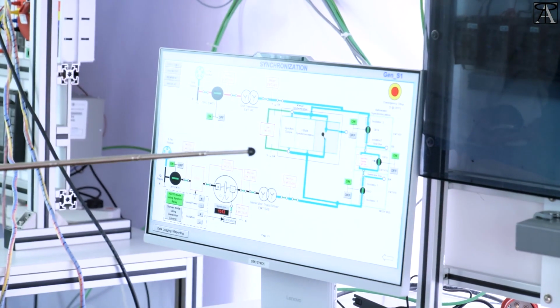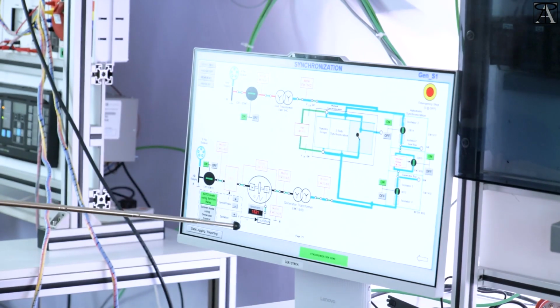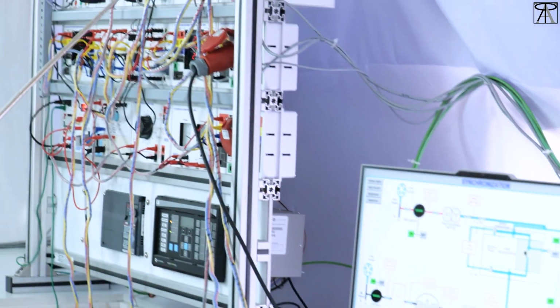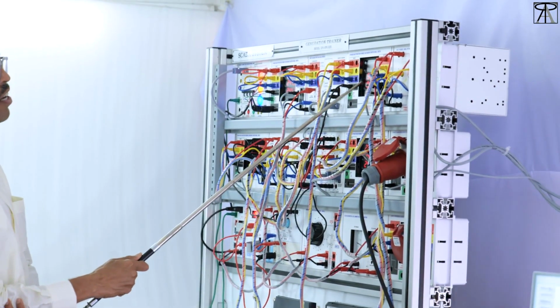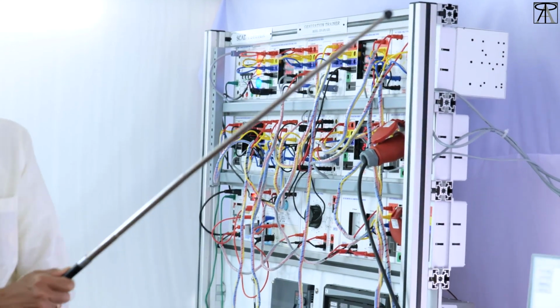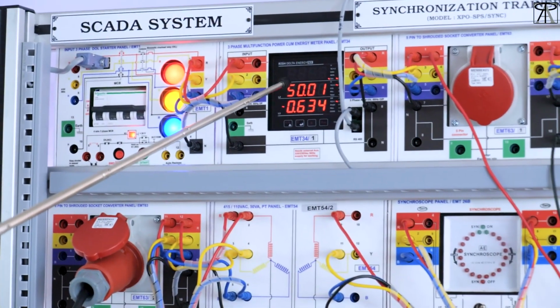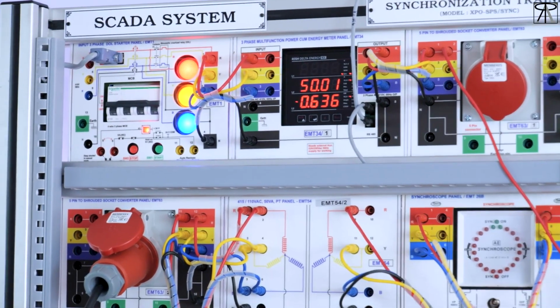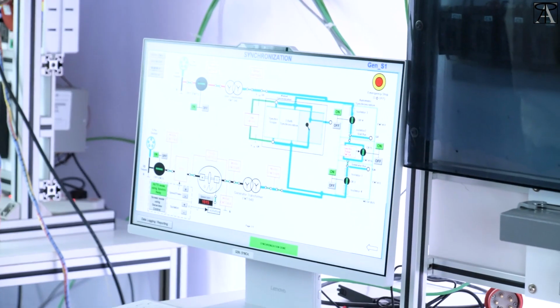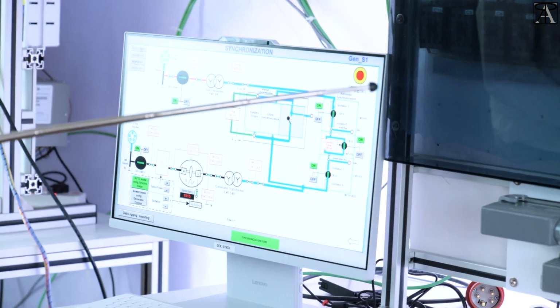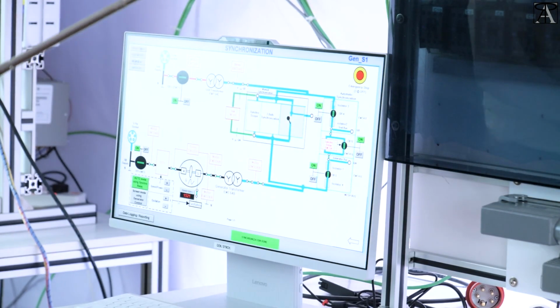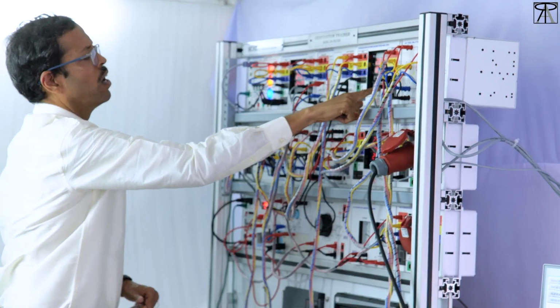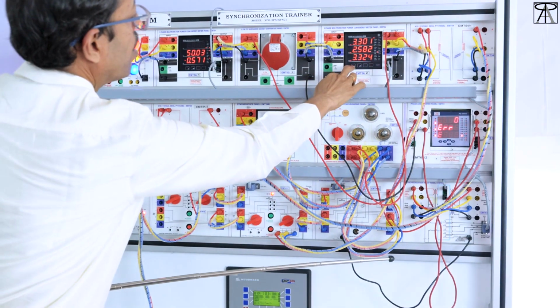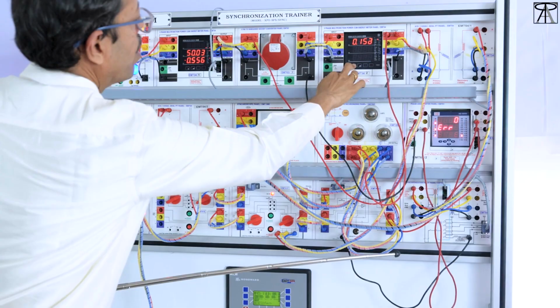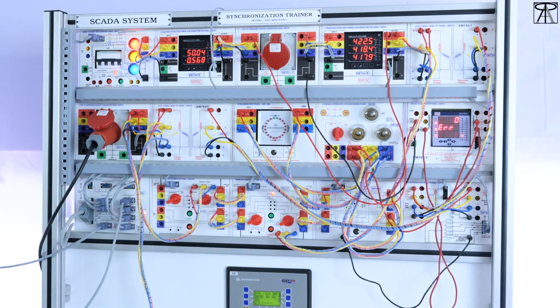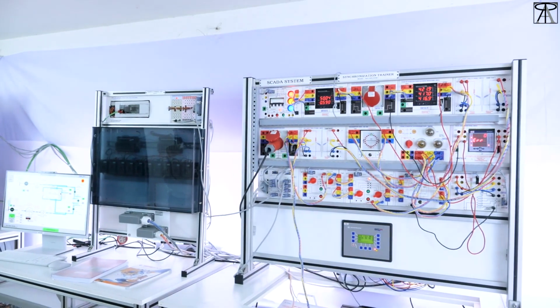So we can check that for synchronization, both power supplies need a common frequency, that is 50 Hz. Here you can see 50 Hz, and here the grid power supply has 50 Hz frequency. Both have the same frequency, which is the reason synchronization has been done. If the frequency is different, we cannot make the synchronization. And you can see the voltages by pressing here: the same voltage, 423 volts, is coming. This is the synchronization of two power supplies, two powers from different places.